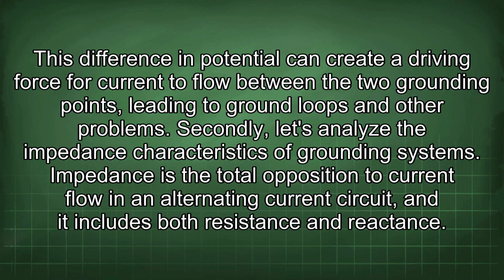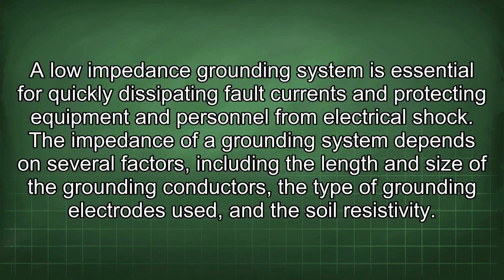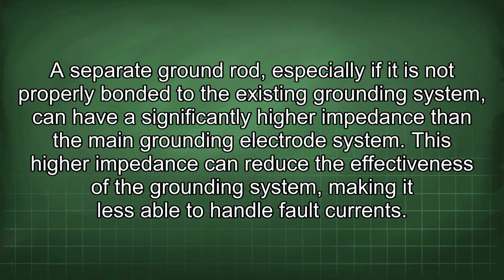Secondly, let's analyze the impedance characteristics of grounding systems. Impedance is the total opposition to current flow in an alternating current circuit, and it includes both resistance and reactance. A low impedance grounding system is essential for quickly dissipating fault currents and protecting equipment and personnel from electrical shock. The impedance of a grounding system depends on several factors, including the length and size of the grounding conductors, the type of grounding electrodes used, and the soil resistivity. A separate ground rod, especially if it is not properly bonded to the existing grounding system, can have a significantly higher impedance than the main grounding electrode system. This higher impedance can reduce the effectiveness of the grounding system, making it less able to handle fault currents.